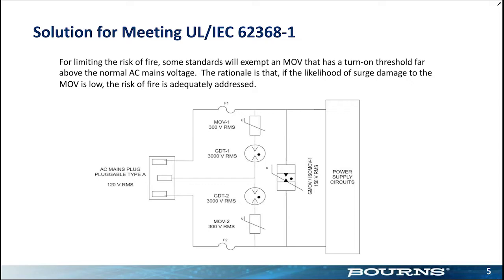What I show here is for common mode surges, right? The surge occurs on both of the outside conductors. Has to get quite large before this thing triggers. And I show a 3 kV GDT, 300 volt MOV, so 3.3 kV is required to turn on that string. I also show on the right a protection for a common differential mode surge, right? The surge occurs across the 2 outside terminals. And that's a strange looking symbol there, and that's what I'm going to be talking about today. It's an IsoMOV or a GMOV device.